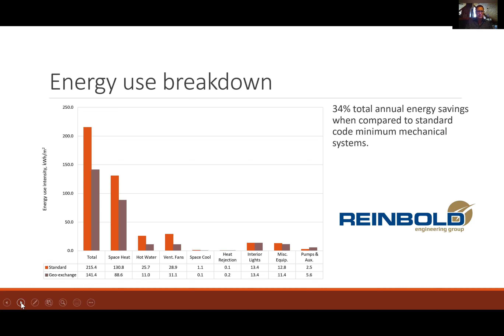We don't have to have a huge cooling tower that costs $500,000, and all the operational costs of running those big fans and pumps and the maintenance of a cooling tower. But he shows a very low load of space cooling, and I truly believe it's a lot higher, but that's what his model pumps out. He's got to run it through the model. And again, this just shows the standard energy use between electricity and gas, and with our building, how we've dropped that down. It's been about a 35% savings in energy consumption just on our mechanical side.